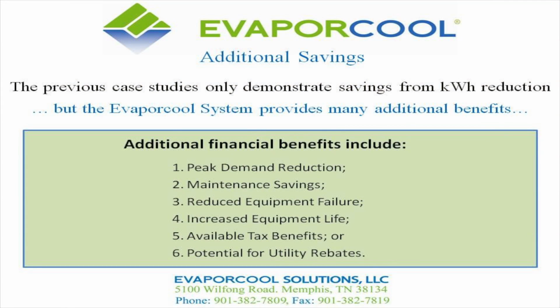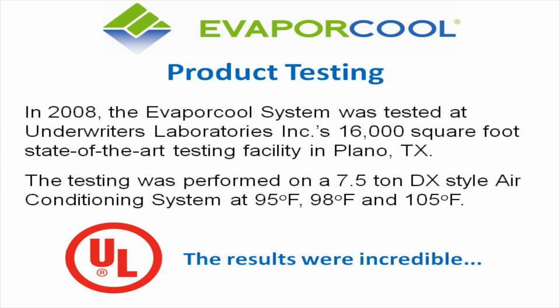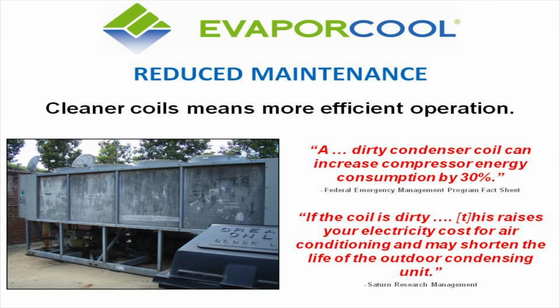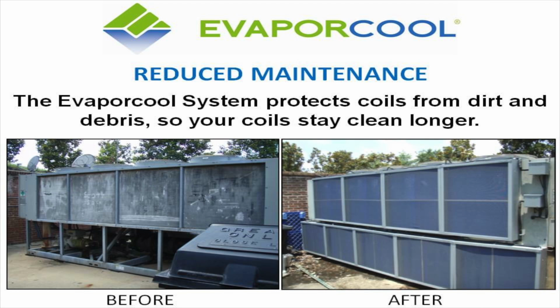When we do an installation, we require that the unit have its coils cleaned, and once those coils are cleaned, we put our system on. Our system protects the coils. It's fair to say that after our installation many building owners don't have to have their coils cleaned again, because there's now a protection where there was nothing before: a filter fabric and a medium protecting everything coming through it. We've been through full UL testing. This is a before and after of a system that clearly hadn't had its coils cleaned in a long time. We did our installation, and you can see the difference in the opportunity to protect those coils.